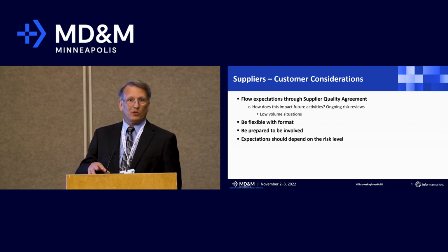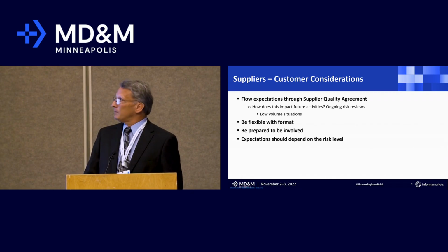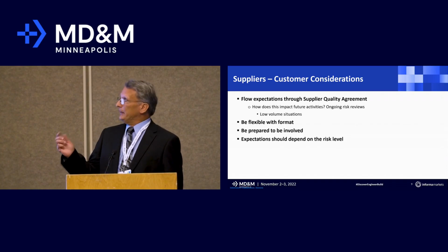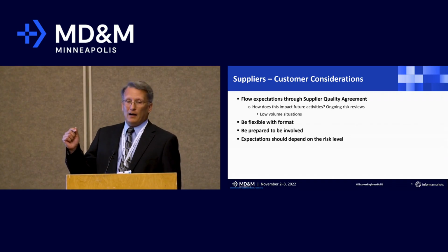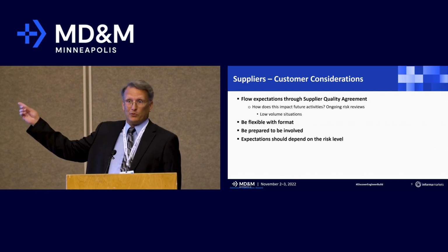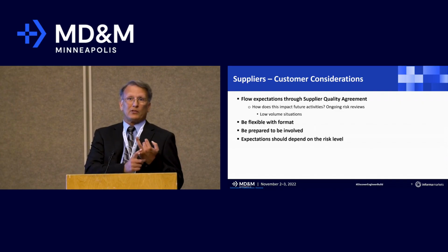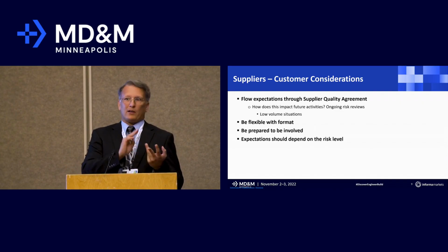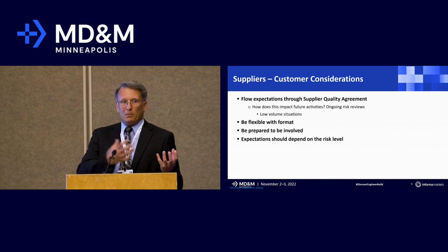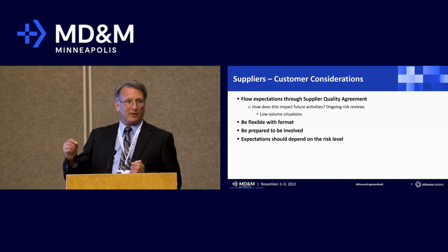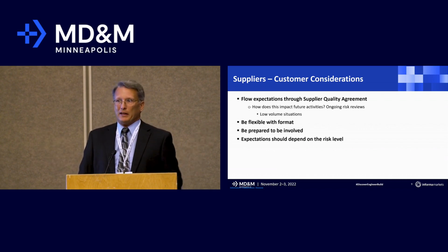Hugely, because the patients are involved here, in the medical device world, you've got to really prepare to be involved. Again, if you're using a supplier template and it doesn't quite match yours, but some of those traceability things for your reports, did all risk activities get completed? Were they satisfactory, and so on? You want to be involved to make sure you can check those boxes with confidence, not just say they took care of it and be hands off.